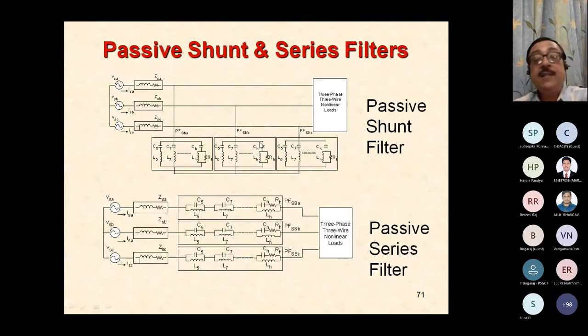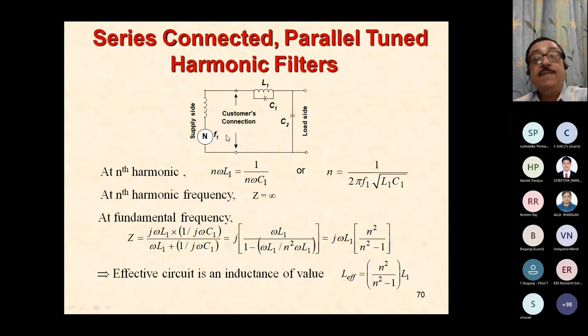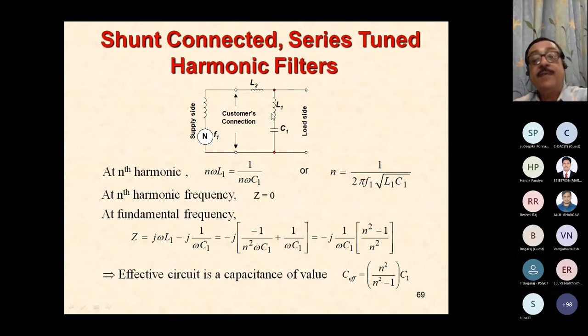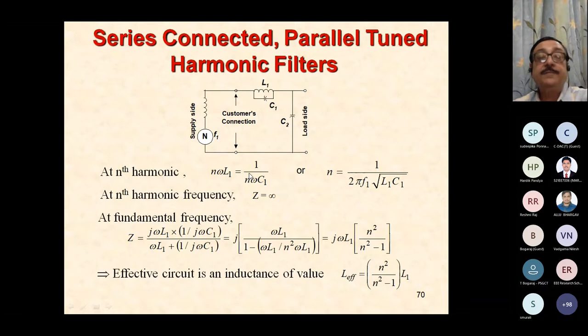The only disadvantage is you have to put one filter of each type for every harmonic frequency. For example, if you need the fifth harmonic, you'll put one for fifth. If you need the seventh harmonic, you need one for seventh, and so on. And for three phase systems, you have everything multiplied by three.